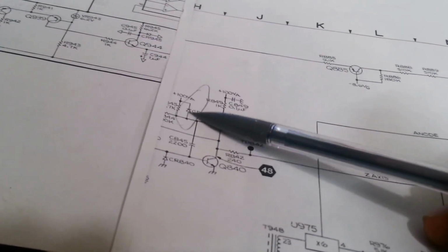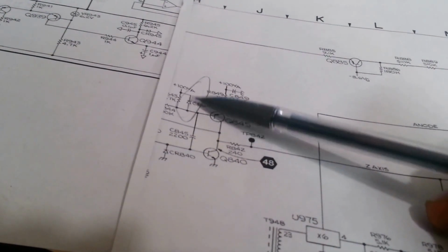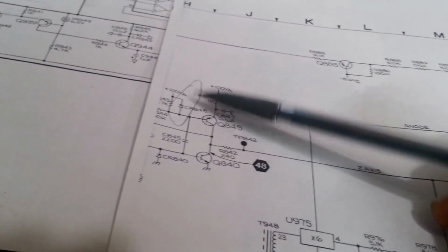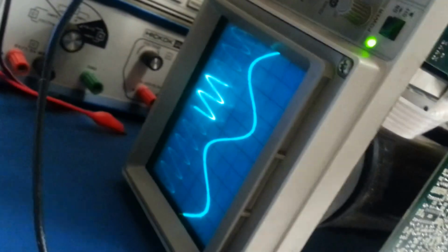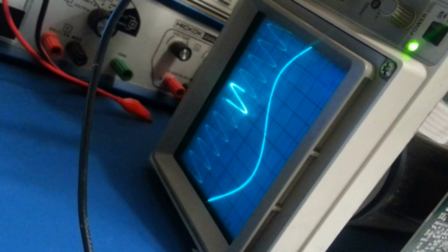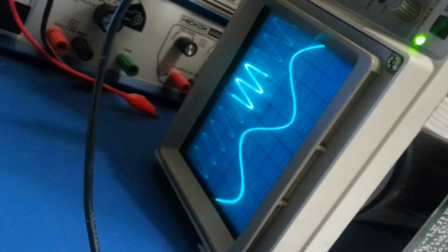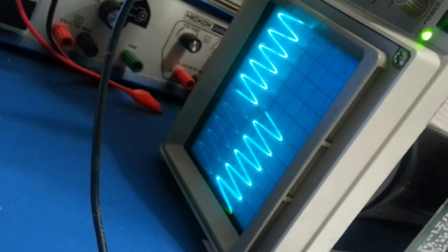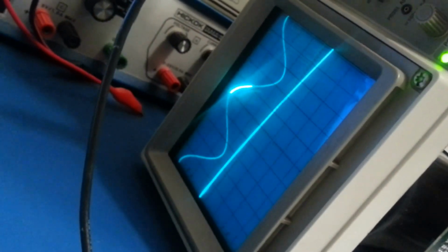It's quite an old school diode, so it's hard to get. But I've found a few on eBay very cheap, so I bought those and they're on the way, so when they come I'll replace it. But yes, it's back, as you can see. It's perfectly back now. The B sweep and the A sweep are both working. You can see I'm in intensified mode where I'm zooming in on part of the waveform.